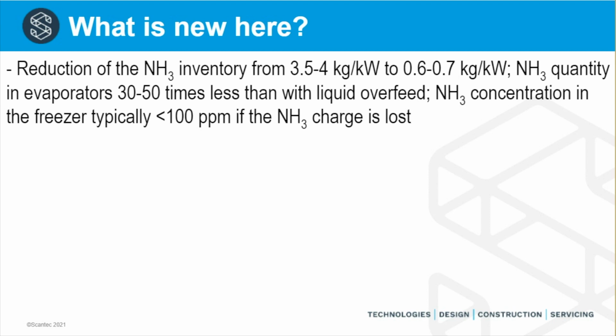Now, if we have a typical freezer with, say, 3 evaporators, and we lose the operating charge of one of those 3 evaporators, it is highly unlikely that the ammonia concentration will exceed 100 parts per million if the mixture is fully mixed. This is on the proviso that the supply of ammonia to the evaporator is terminated immediately upon detection of the leak, and it is also assuming that the air refrigerant mixture in the warehouse is completely mixed. Now, the IDLH value of ammonia is about 300 parts per million. There are some moves to raise that to 500 parts per million. So we will be significantly lower than the IDLH value if we have a low temperature ammonia system, and if we should be unlucky enough to experience a leak. IDLH stands for immediate danger to life and health.